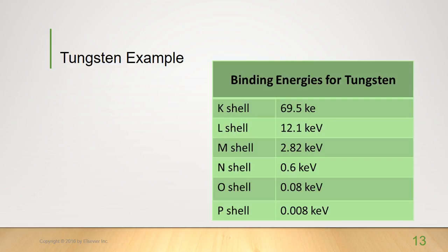So for all practical purposes, using a general purpose X-ray machine, if a radiographer selects a kVp less than 70, then there are going to be no photons produced from the K-shell interaction because we use tungsten as the target, and it has to be at least this, so 69.5. And if you have less than that, it's not strong enough to knock that K-shell out. That's how this all works. And that's important for you to remember, because then when we talk about the beam quality and the quantity, it'll make sense to you.